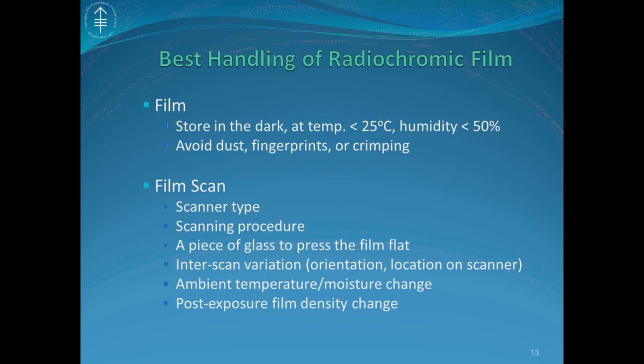For film scanning, a medical-grade film digitizer, such as VIDAR, or a document-type flatbed scanner, such as Epson, should be used. Besides being much less expensive, the flatbed scanner would have an option for multi-channel dosimetry because of its 48-bit RGB color. However, there are lots of rules for using a flatbed scanner to achieve accurate dosimetry. For example, placing a piece of glass on it, pressing the film flat, and keeping the same orientation and location on the scanner for both calibration and the QA film.